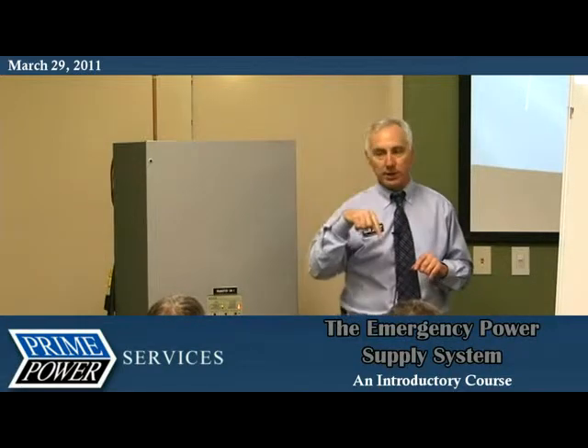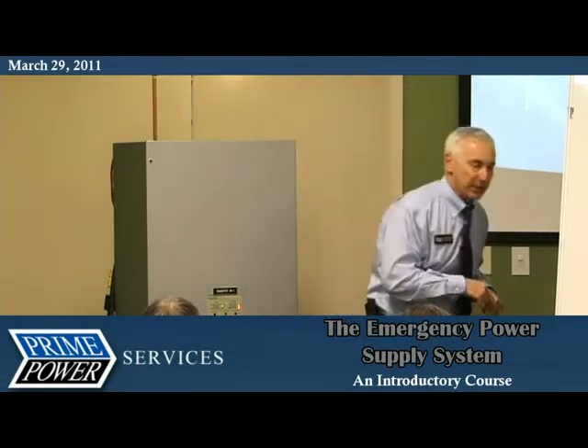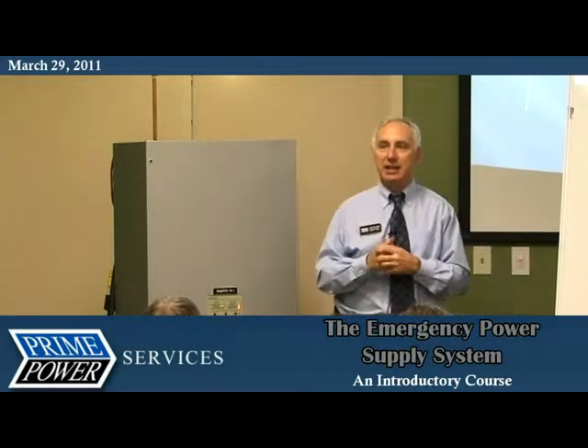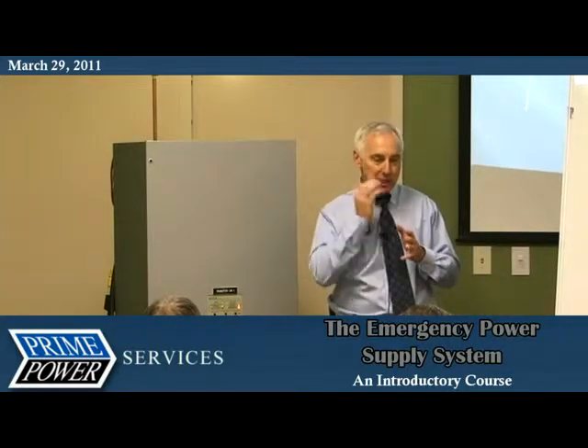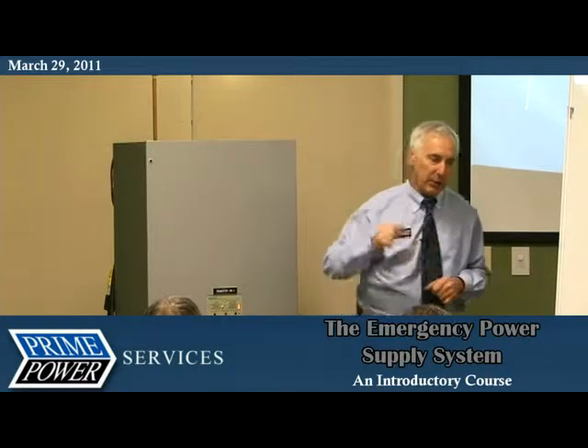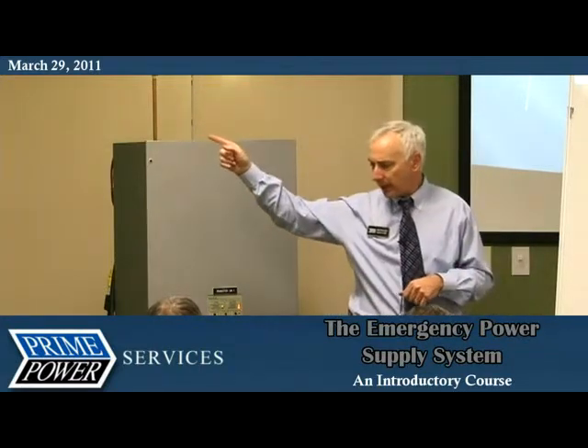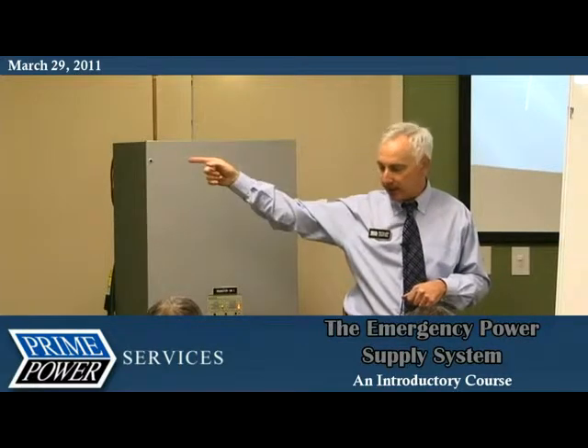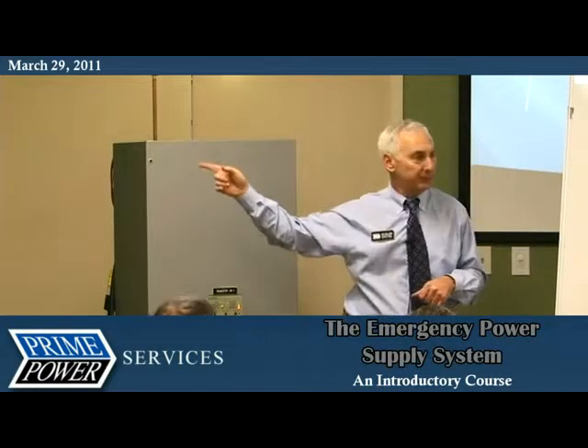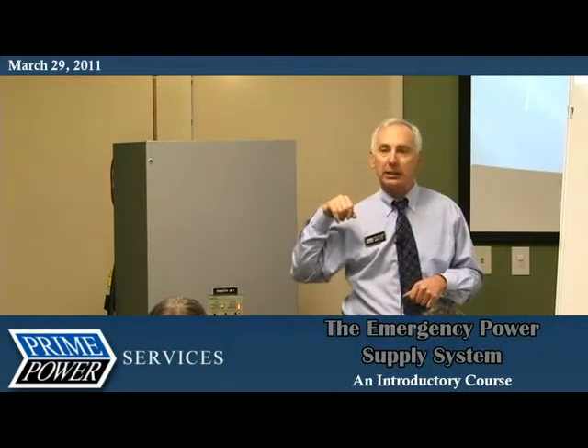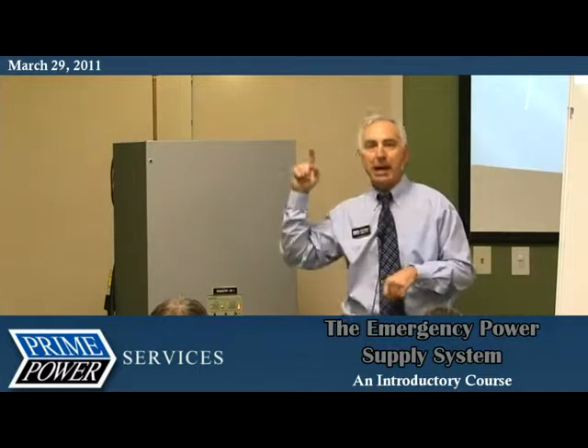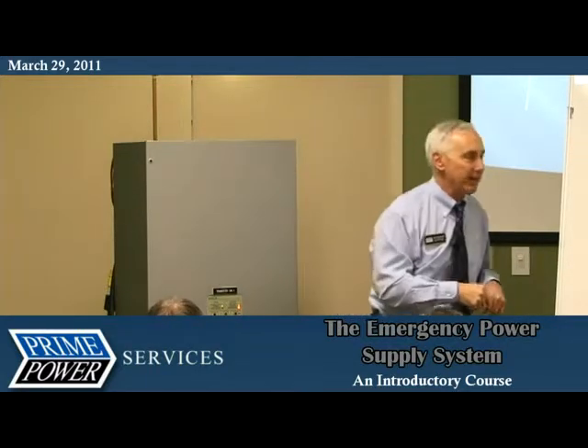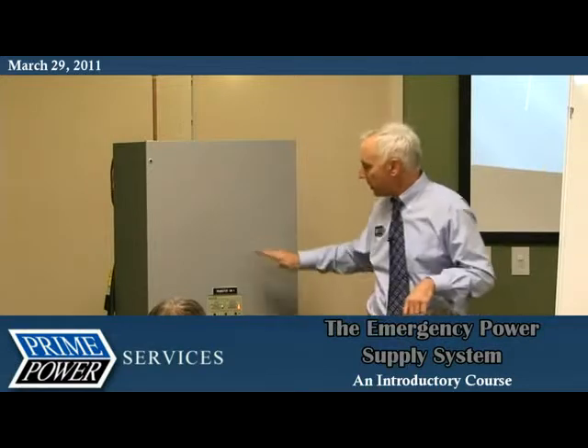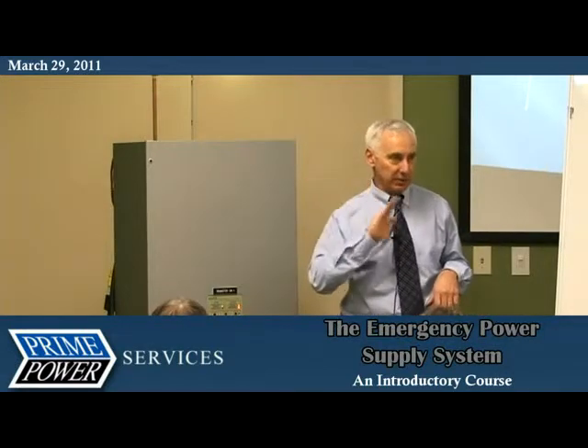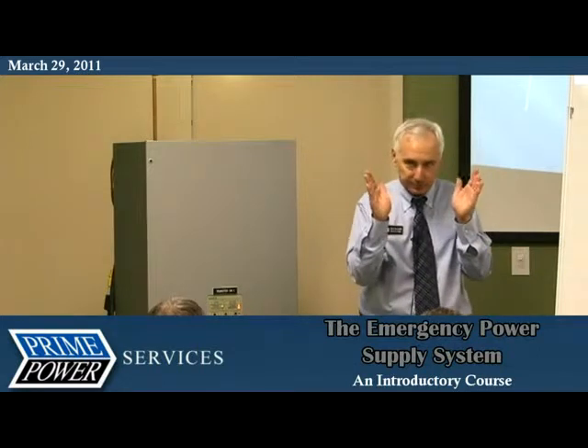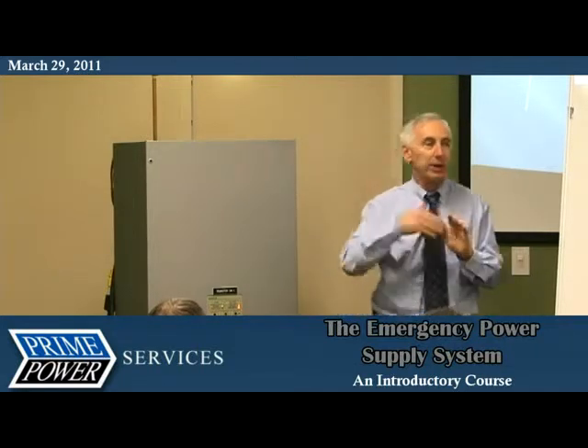Then, once normal returns, there's a return to normal time delay. Typically, that's set at 30 minutes. It can be less. The purpose of that return to normal time delay is that when we have an outage out here and a tree has hit a power line due to an ice storm, and the power company is out there reconnecting lines, they may get that connected, but then disconnect it 5 minutes later because they're redoing a bunch of stuff. So we want that retransfer time delay to normal to be such that we're sure we've got good normal power. Then we allow it to go back.